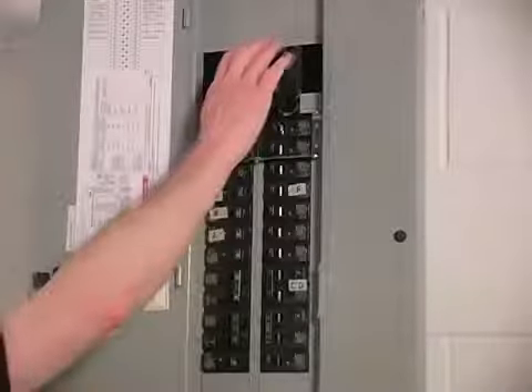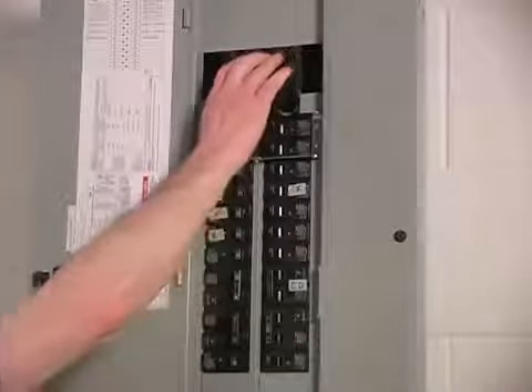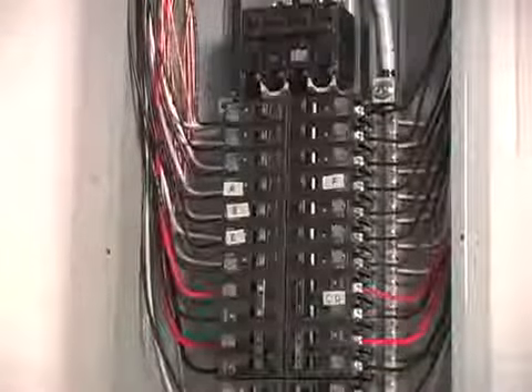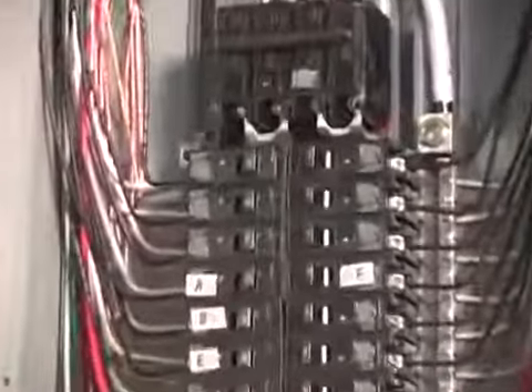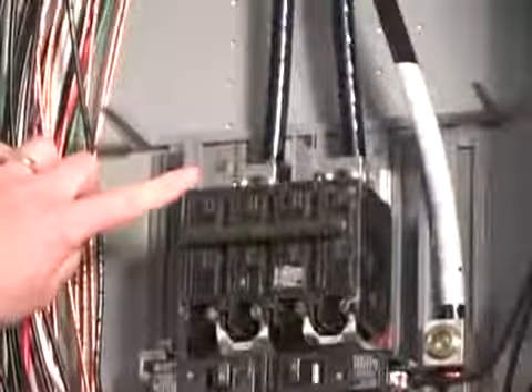Next step is to remove the cover from the main panel, but first we want to be sure to turn off the main circuit breaker. This will cut off power to the entire house, and you may need a flashlight from here on. Please be aware that even though this panel is off, there is still live power at the top where the utility power comes in.